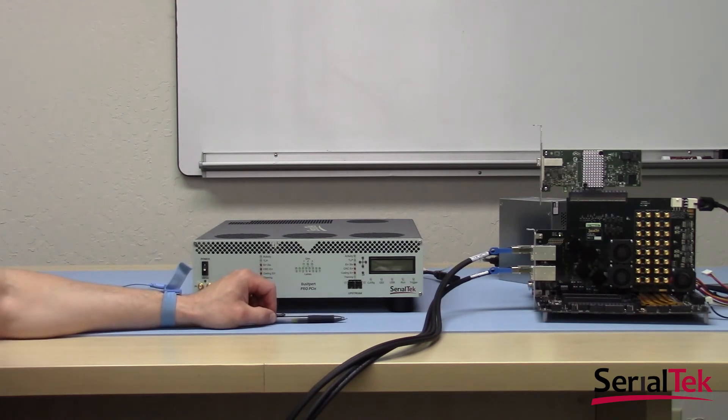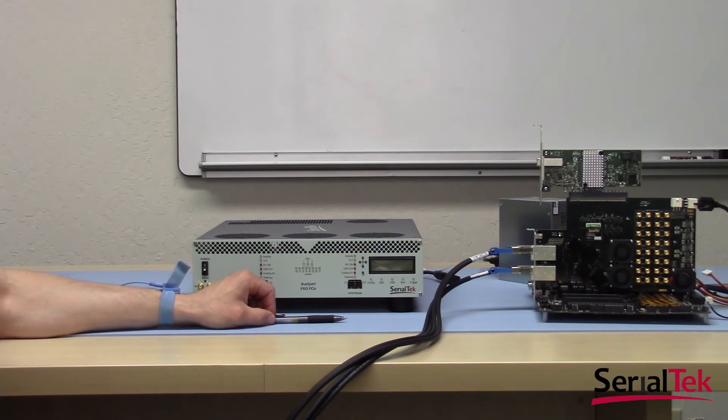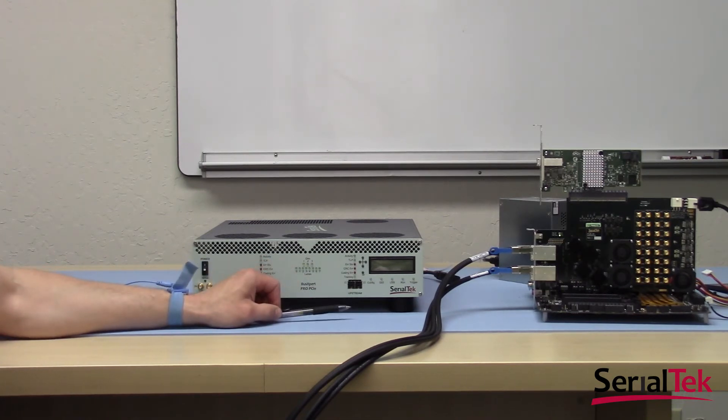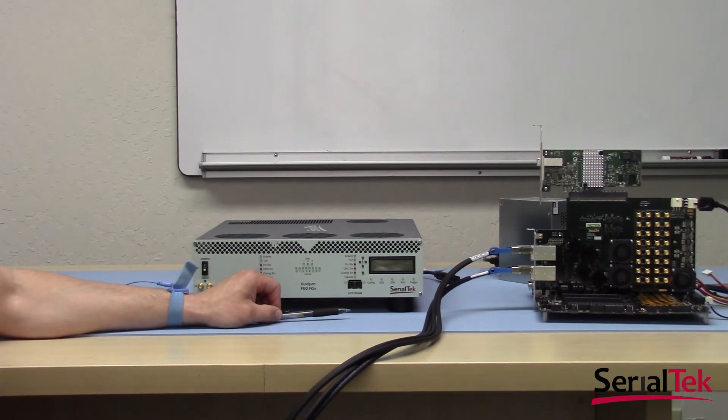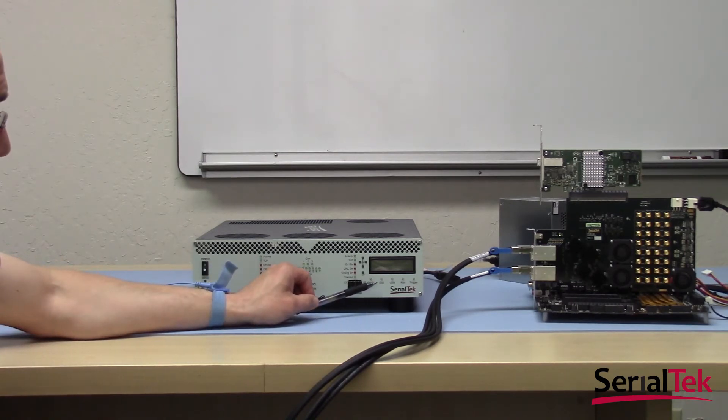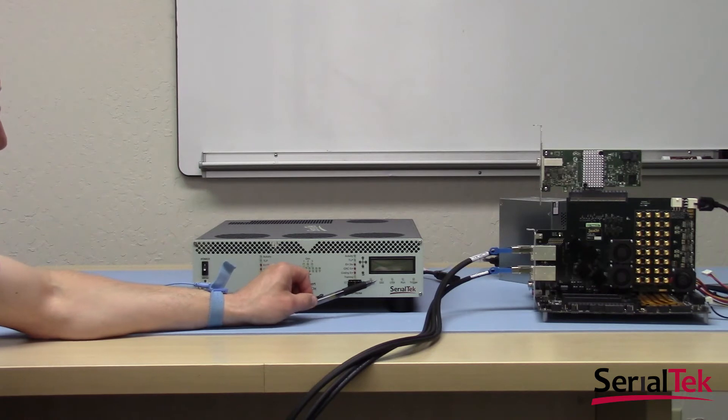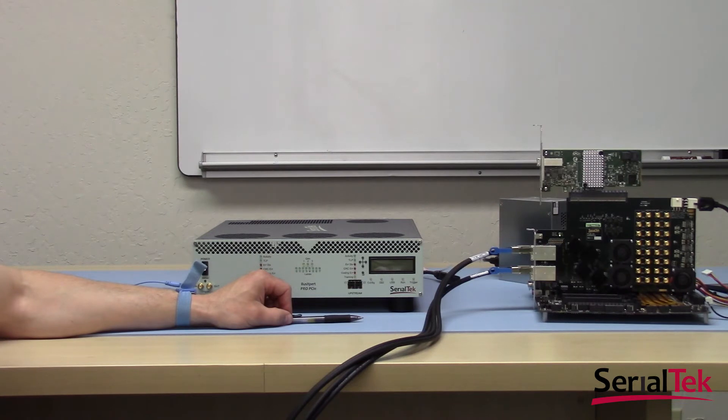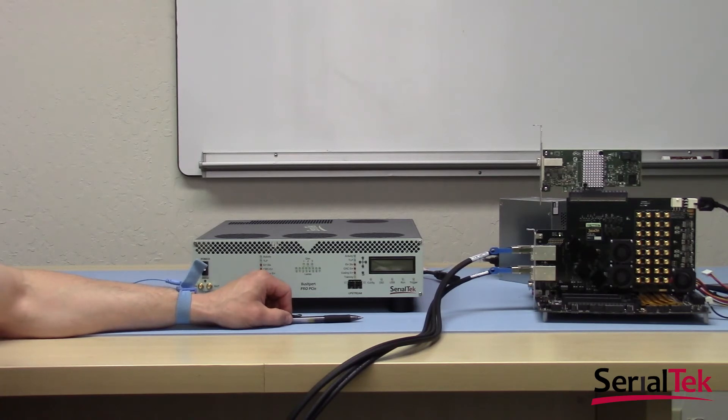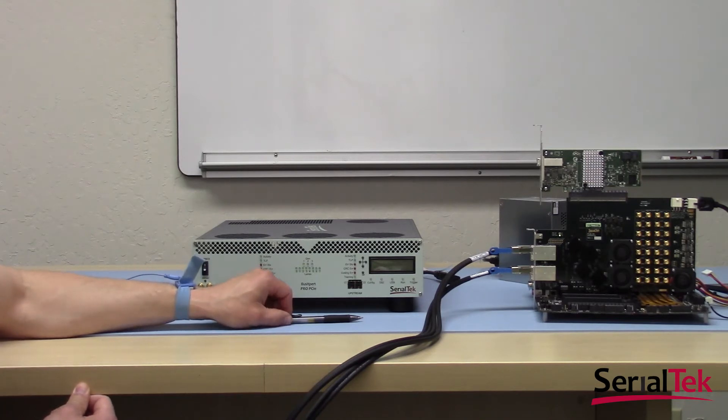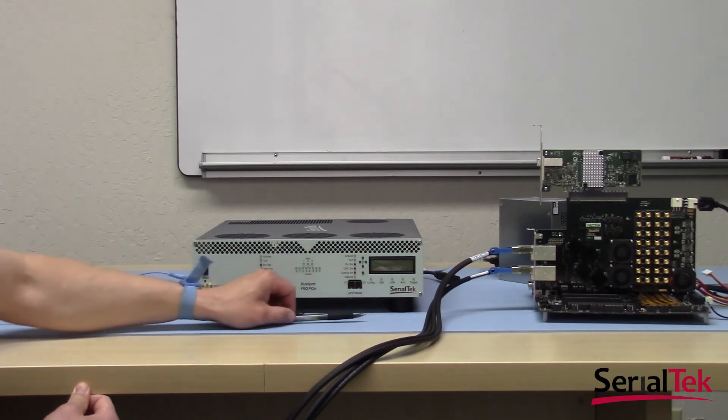Next to that is the Gigabit Ethernet LED. This light is off when there's no Gigabit Ethernet connection. Incidentally, when there's no Gigabit Ethernet connection, the IP address will read 0000. When you have an IP address, then the Gigabit Ethernet light will be one of three colors. Red for a 10 Mbps Ethernet connection, yellow for a 100 Mbps Ethernet connection, and green for a 1000 Mbps Ethernet connection.